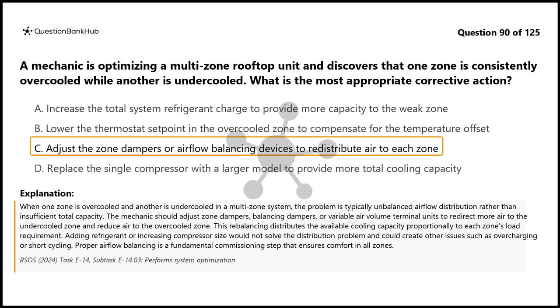This rebalancing distributes the available cooling capacity proportionally to each zone's load requirement. Adding refrigerant or increasing compressor size would not solve the distribution problem and could create other issues such as overcharging or short cycling. Proper airflow balancing is a fundamental commissioning step that ensures comfort in all zones.